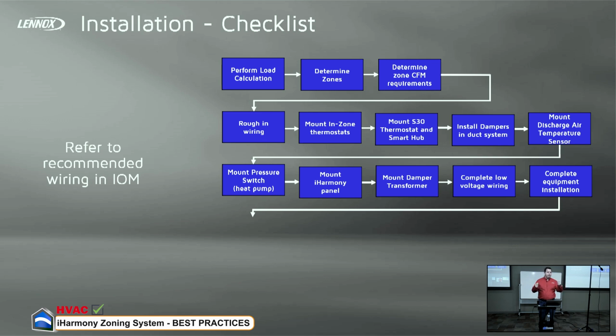If you've got all your wires run, got everything labeled and know what's where, that will help avoid a lot of confusion, because, as we'll go into a little bit later on, a lot of times guys go out and install these with a roll of 8 wire. That'll make you want to cry. I did a field site visit one time with a dealer who was having issues with one of these, and it was 8 wire for each damper, 8 wire for each zone sensor, 8 wire for everything. You had all these conductors and it was hard sorting out what's what. Nothing was labeled on it, and so it just made things a nightmare. So taking that step, being precise about it, and making sure we know what's what coming in there is really going to help you sort through issues. Because if you've got 20 different wires coming at you, it's hard to tell what's what.